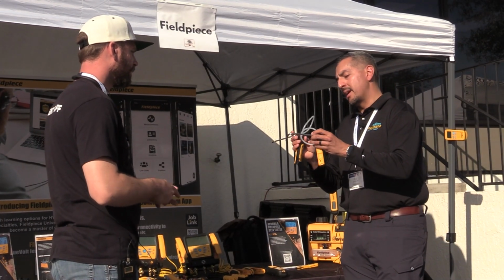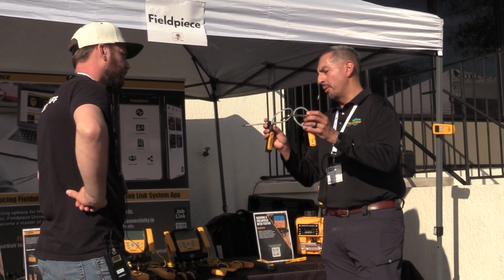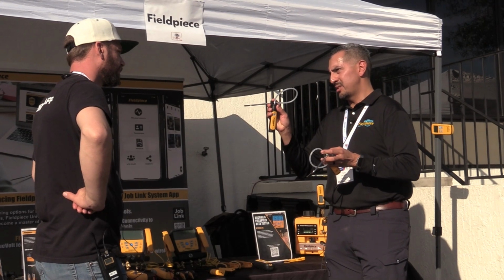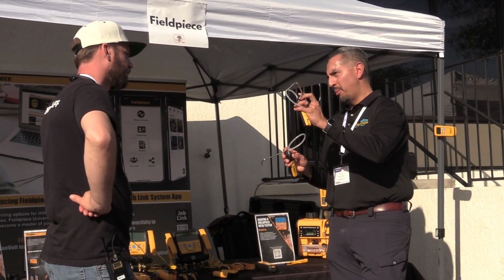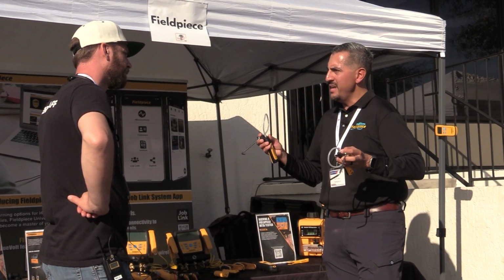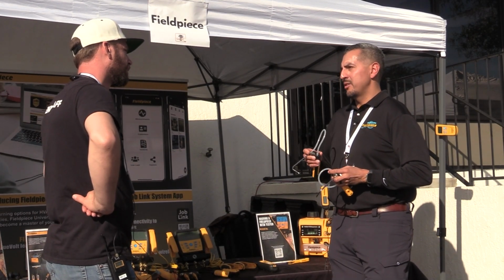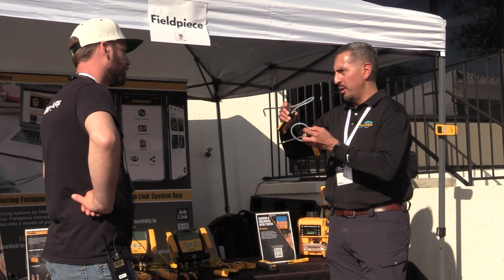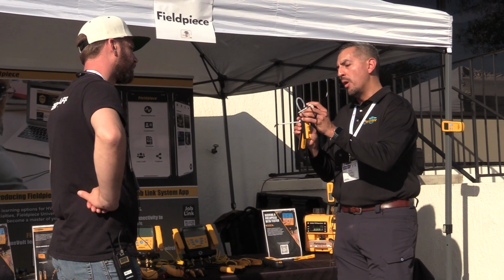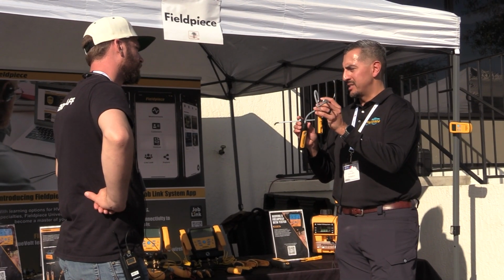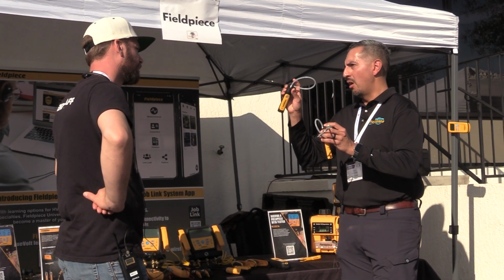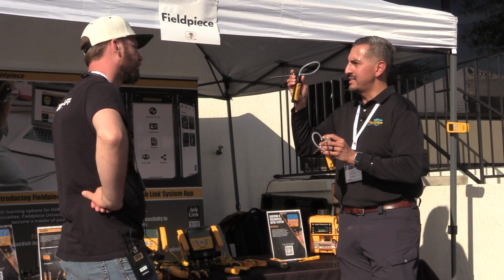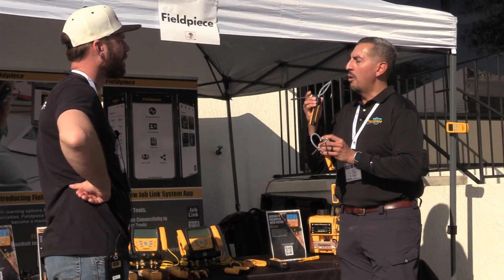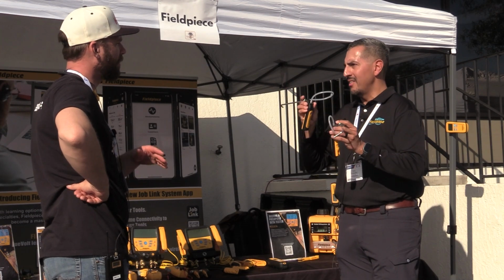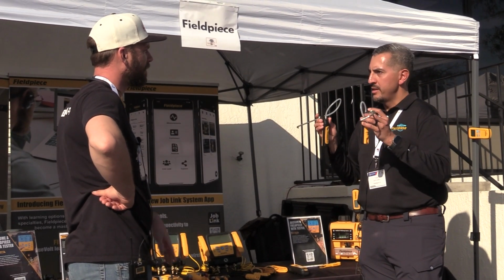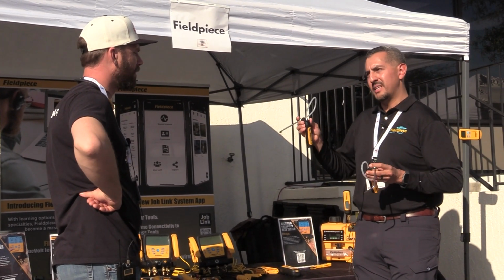Another pro tip when it comes to separating a dual port is you have an independent pressure sensor for your P1 and an independent pressure sensor for your P2. That means you not only get total external static pressure when you add those up, but now you know what the pressure is on the supply side versus the return side. So if you have high static, you know which side of the system is worse.